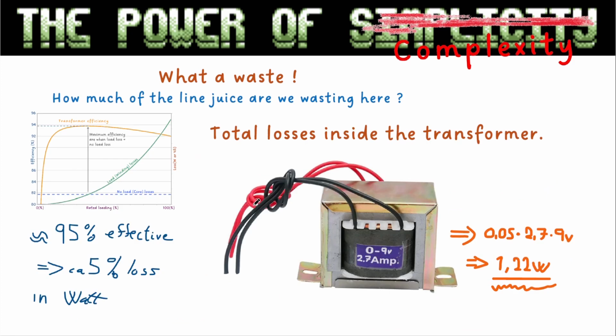If we put some numbers into this, we see that with 5% loss the transformer produces 1.22 watts of heat when the total power is drawn. We do have some other measurements that state this is a bit higher, but it's still below 1.5 watts with the nominal current draw.